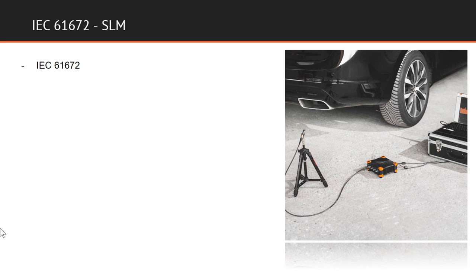As we have established the meaning and importance of performing the calibration itself, let's focus next on particular calibration procedures and their corresponding standards. We will begin with one of the most widely used and performed calibration services, Class 1 sound level meter calibration of the measurement chain according to IEC 61672. IEC 61672 is the standard that is most often used when it comes to calibration of sound level meters. Procedures include tolerances and are designed to verify that the characteristics of the sound level meter are correct.